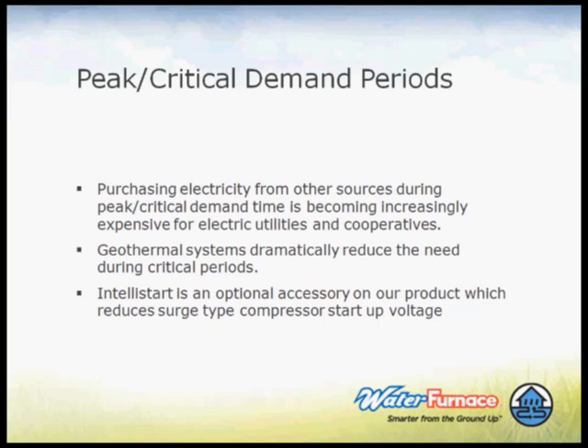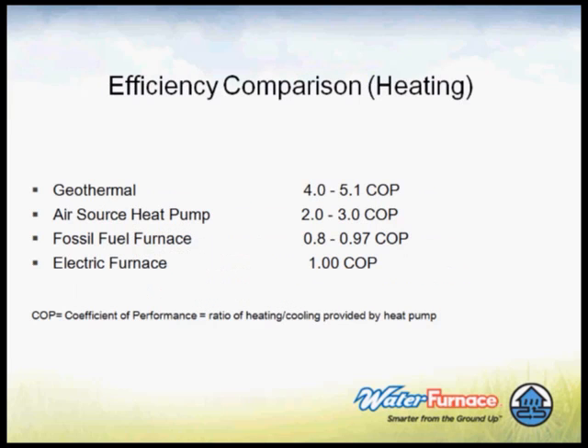The second worst time is in the coldest days of the winter. So we reduce that peak heating demand because we're using so much less energy on a 95-degree day to put that heat in the ground than it takes to put it into the air. So we reduce that need. We also have a product called IntelliStart, which reduces the voltage. It's technical, but to start that compressor up, we reduce that locked rotor amps, it's called, by as much as 70%. So the power companies should be all over that. And tell the house that when the unit comes on and dims your lights, this will take care of it.